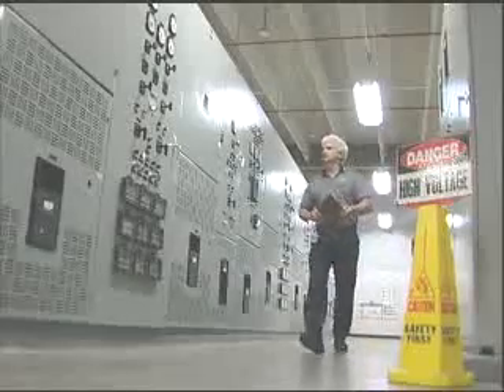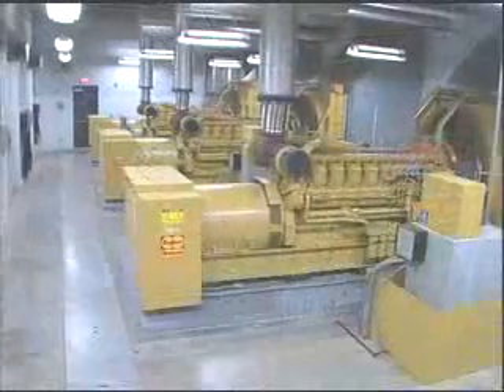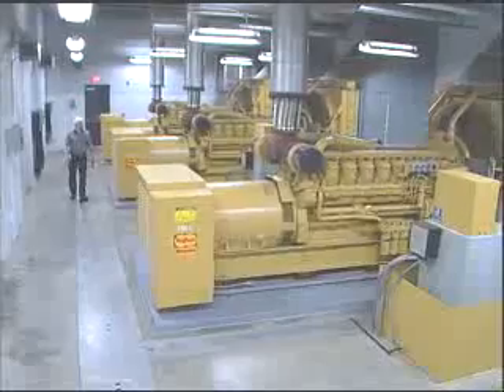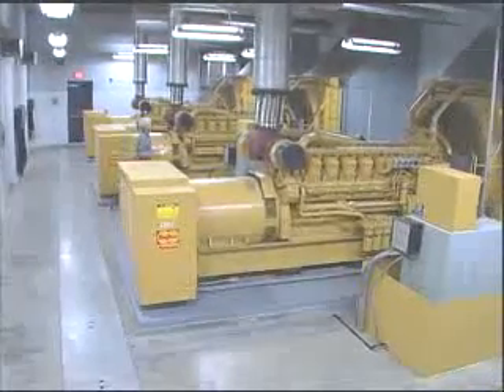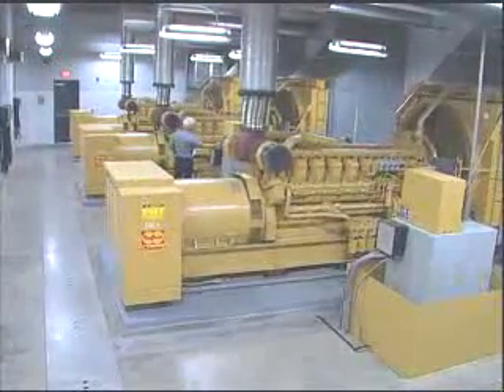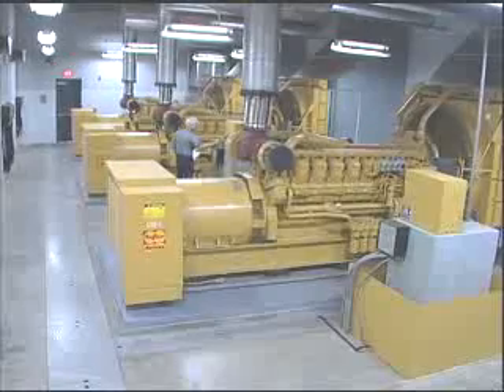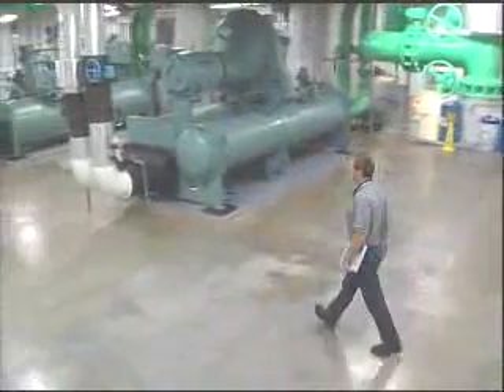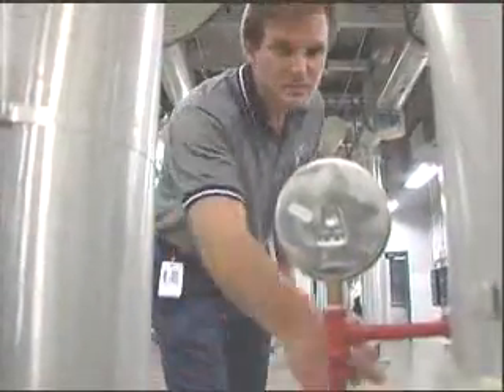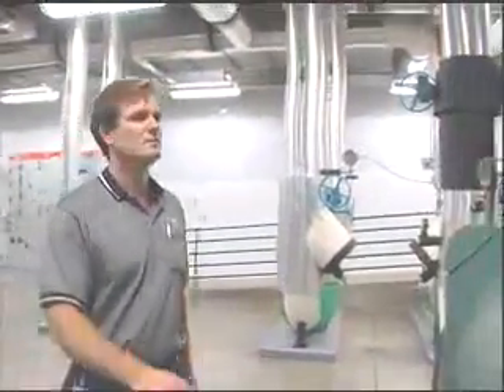The UPS system is comprised of 3 motor generator units. These units operate in a parallel mode via a system called the ring bus. Any one of these units can support the total power requirements of our IT systems. The heating, ventilation, and air conditioning system is provided by 2 fully redundant 850-ton chilled water units.